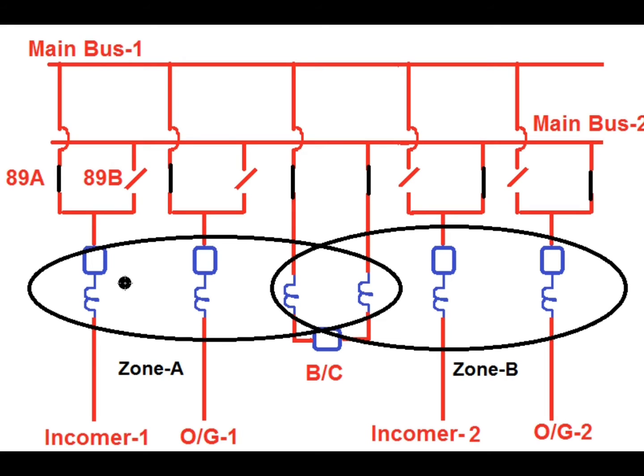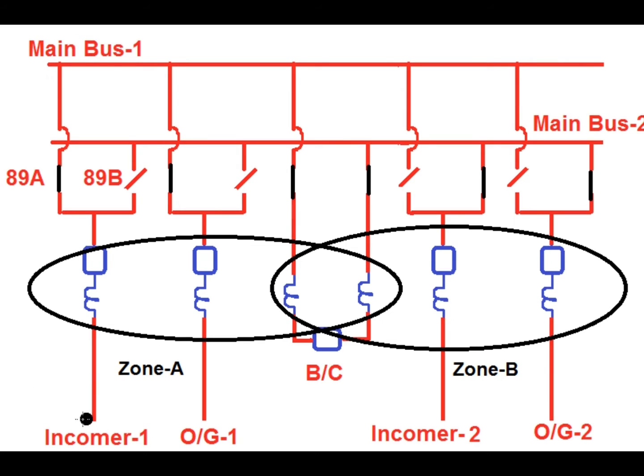How does the bus bar relay sense the fault at either zone A or zone B? The answer is by isolator selection. If the isolator is connected towards main bus 1, it will be counted as zone A. If the isolator is connected towards main bus 2, the current will be considered as zone B. The isolator has an auxiliary switch, and the auxiliary switch status is connected to the relay. If incomer 1 is connected towards main bus 1 via 89A, then the 89A status goes to the relay and incomer 1 is considered in zone A.